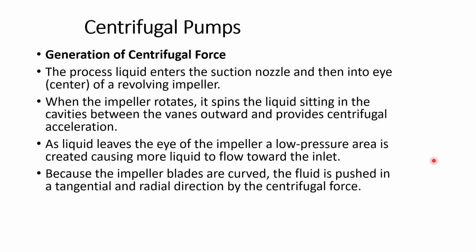Centrifugal pump generation of centrifugal force: the process fluid enters the suction nozzle and then into the eye or center of the revolving impeller. When the impeller rotates, it spins the liquid sitting in the cavities between the vanes outward and provides centrifugal acceleration. As liquid leaves the eye of the impeller, a low pressure area is created, causing more fluid to flow in towards the inlet of the impeller. Because the impeller blades are curved, the fluid is pushed in a tangential and radial direction by the centrifugal force.